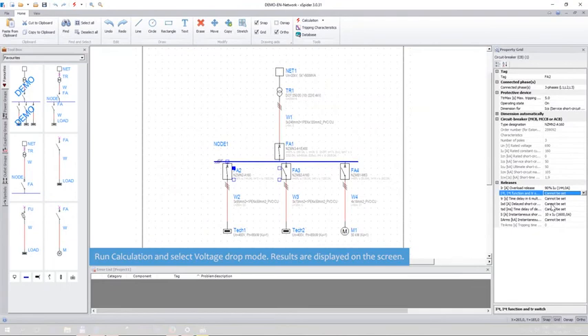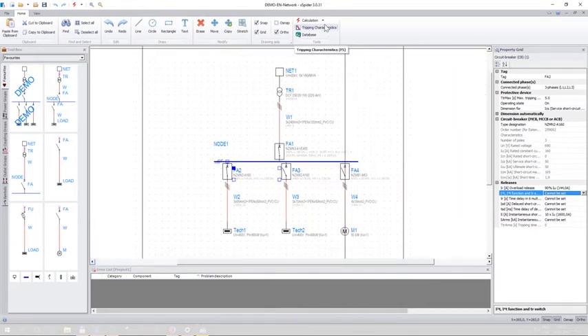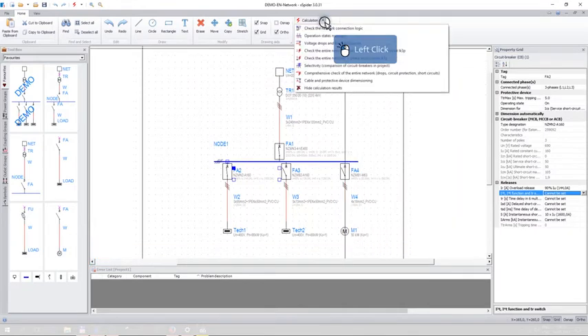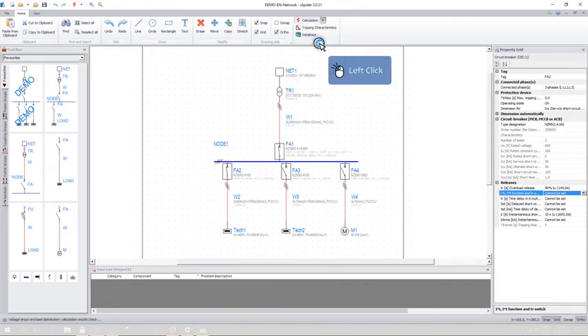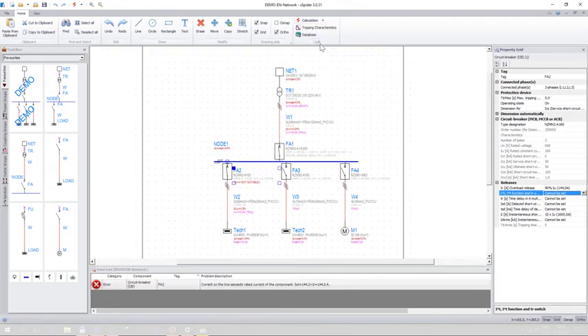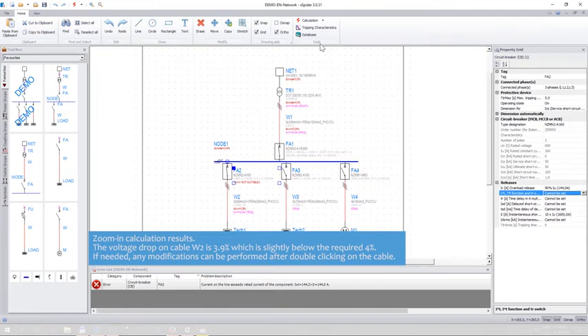Run calculation and select voltage drop mode. Results are displayed on screen. Zoom in calculation results. The voltage drop on cable W2 is 3.9%, which is slightly below the required 4%.